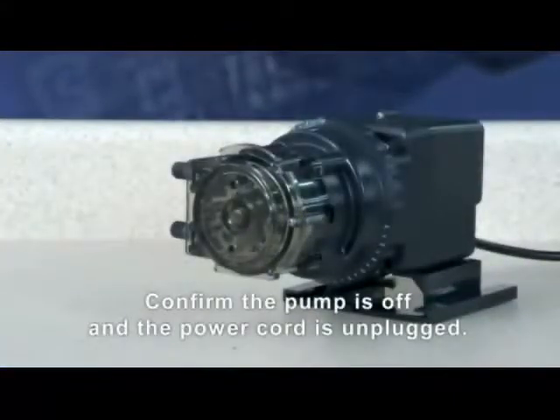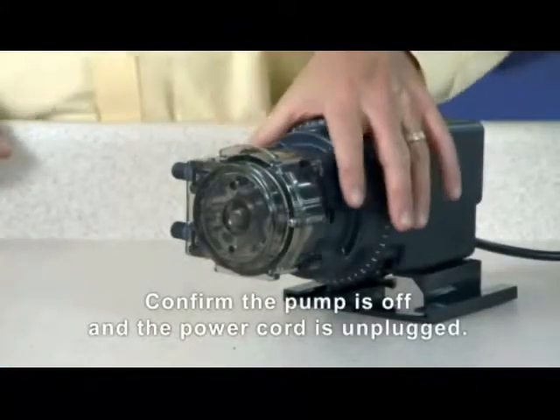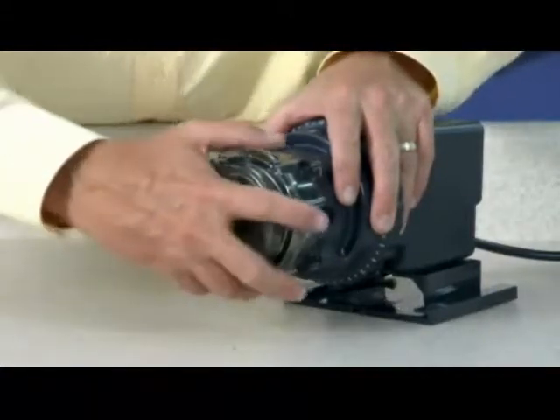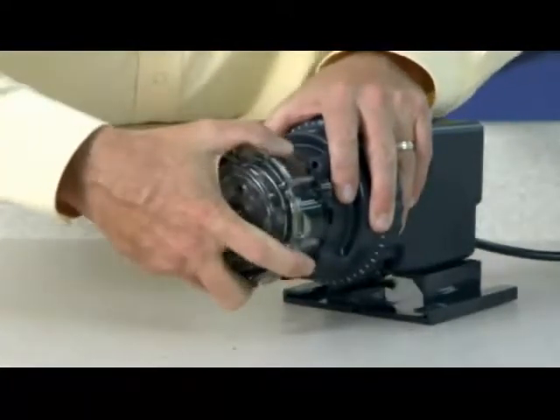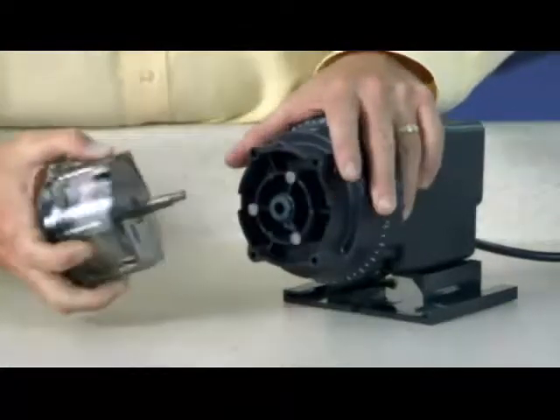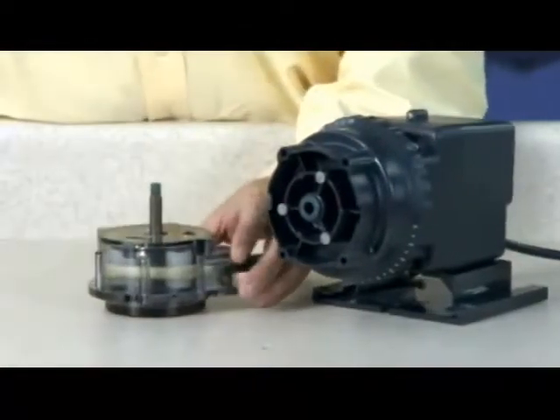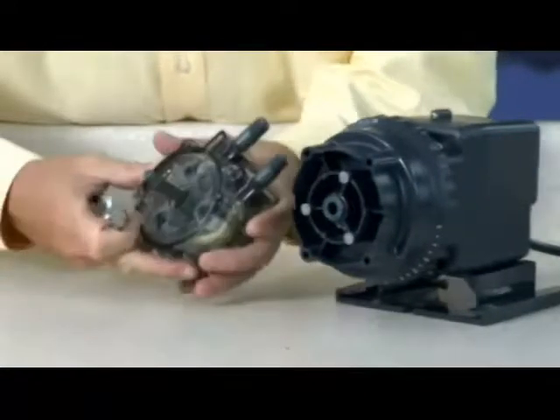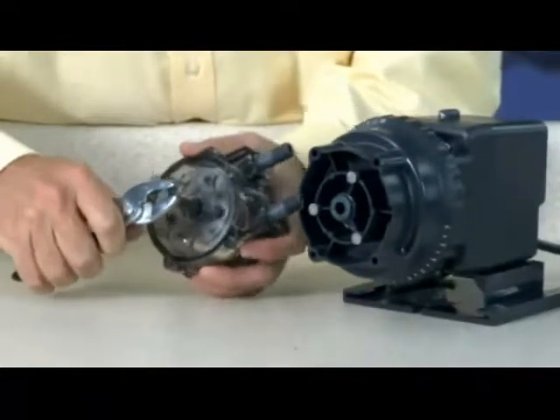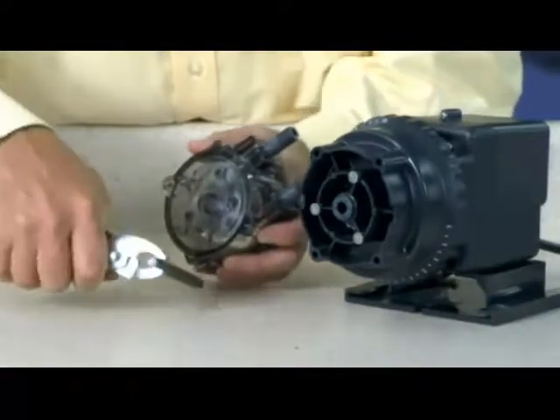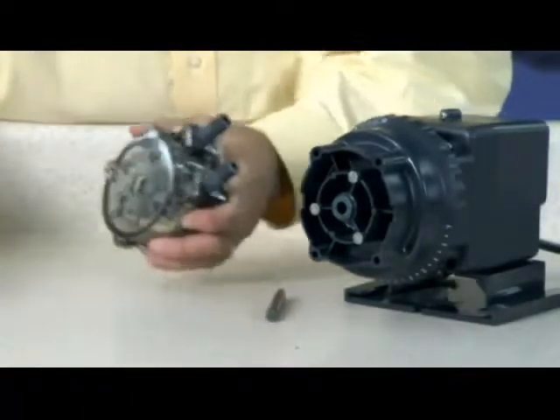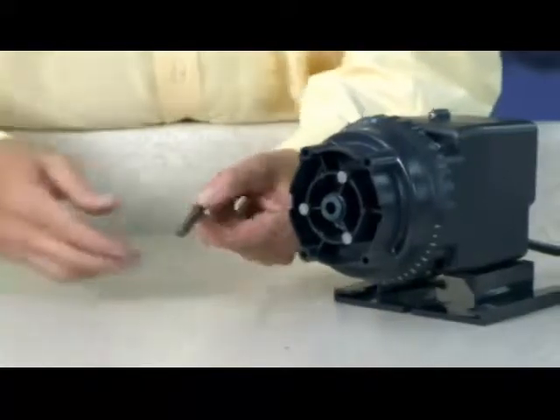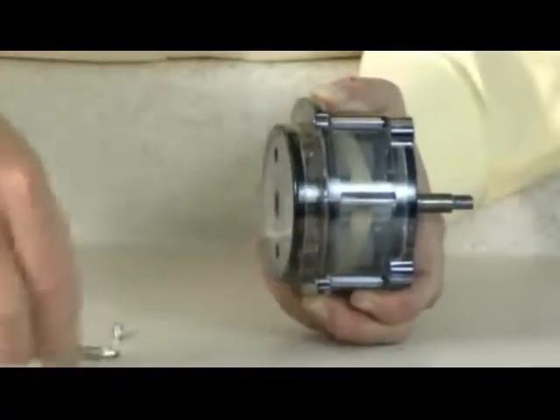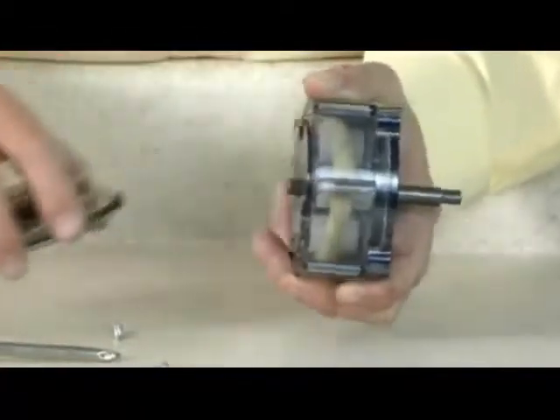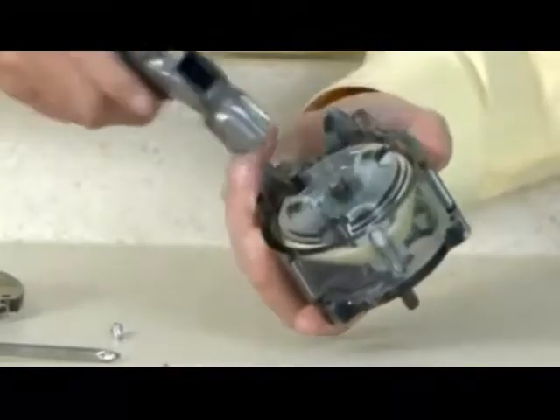To remove the pump head, hold the feed rate securely. Grasp the head and turn it clockwise until it stops. Remove the head by pulling it straight out from the pump. The main shaft will come out with the pump head. Using a pair of pliers, grasp the main shaft and rock it back and forth, clockwise and counterclockwise, while pulling it straight out of the pump head. Set aside the shaft to be reinstalled later. Discard the old tube, housing, and cover. If the shaft will not come out, remove the cover from the pump head and use a hammer to tap the shaft from the front of the roller assembly to dislodge it.